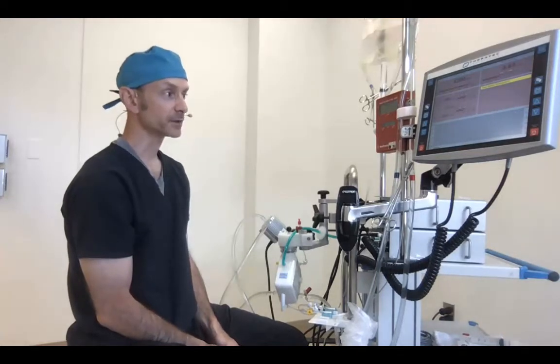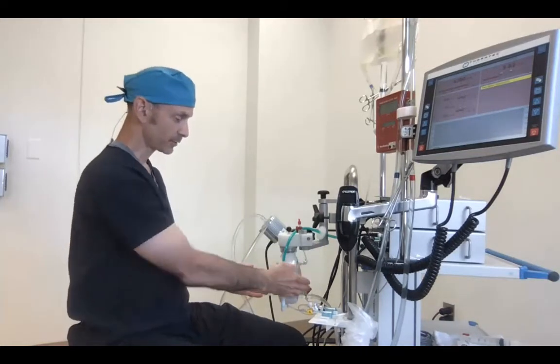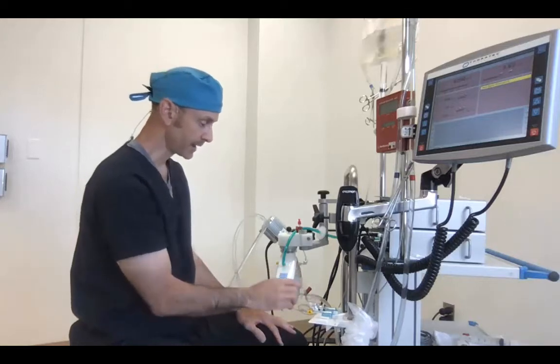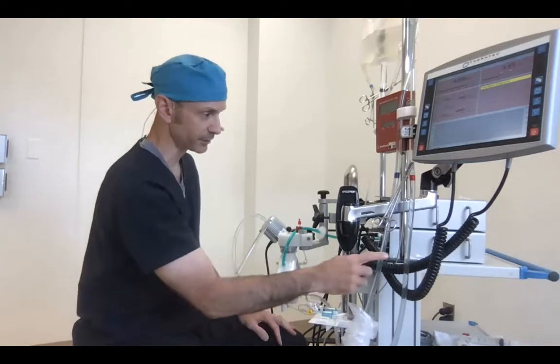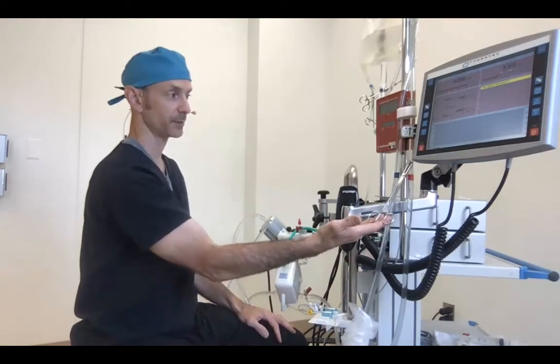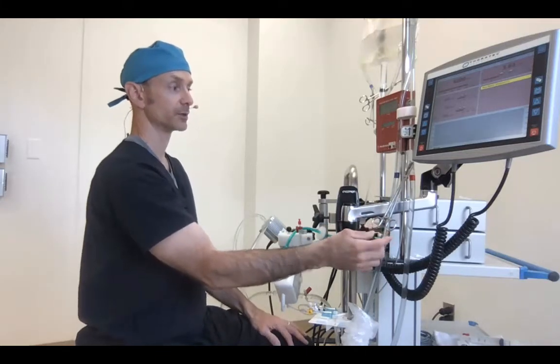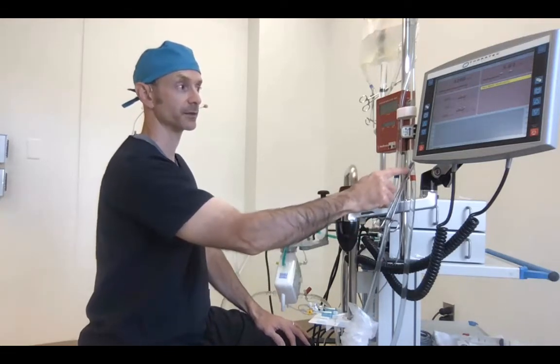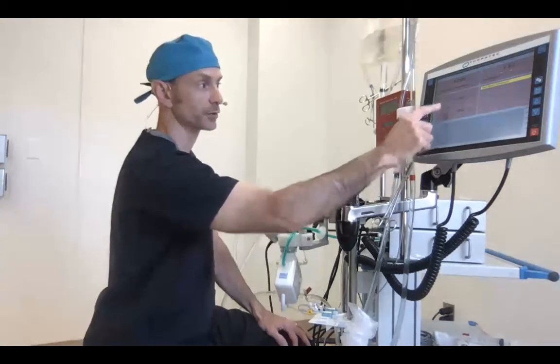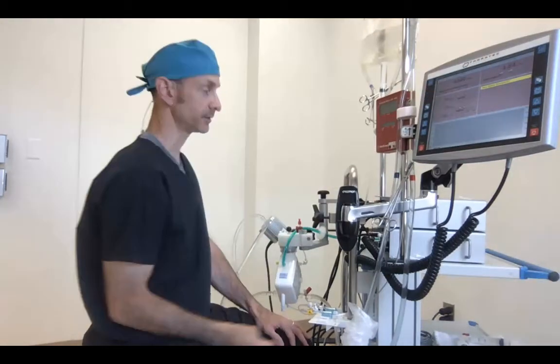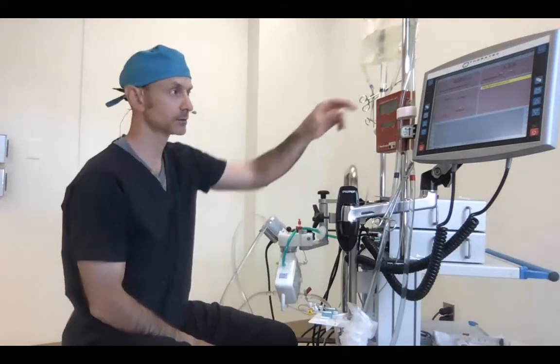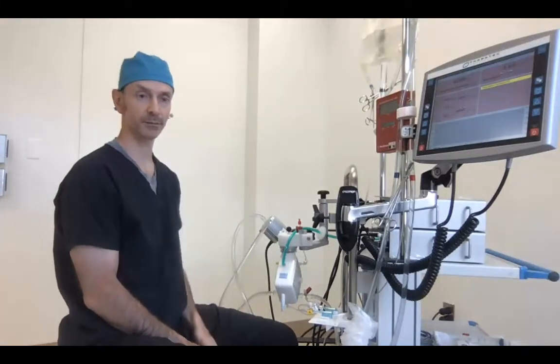On the other hand, if you look at the pre-membrane and post-membrane pressures, they can see the oxygenator, the arterial line, the cannula, and the patient, and there's a clamp on that arterial line. So what they see is a higher resistance. That higher resistance causes the pressures to go up and the flow to come down on this afterload dependent pump.